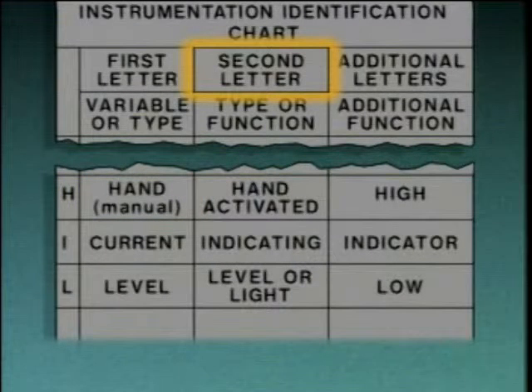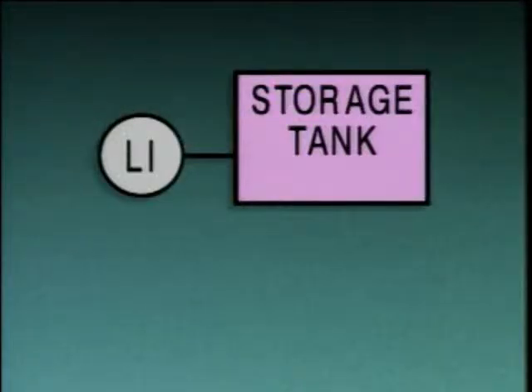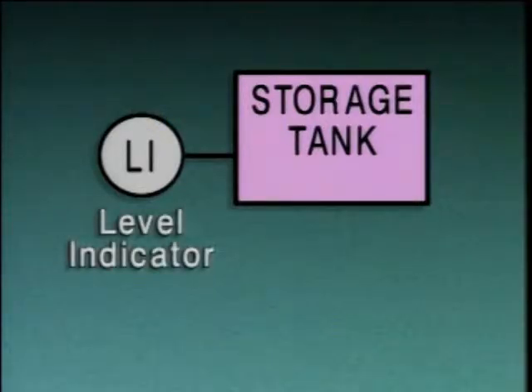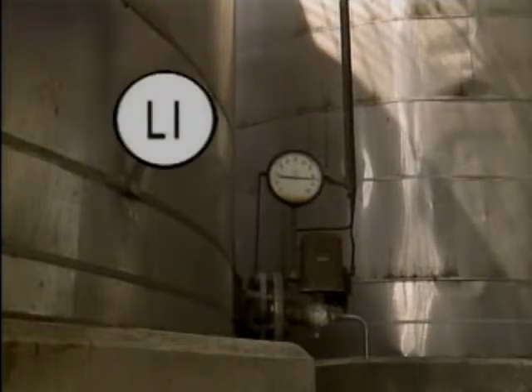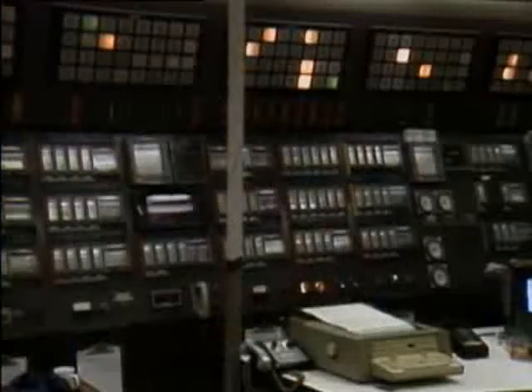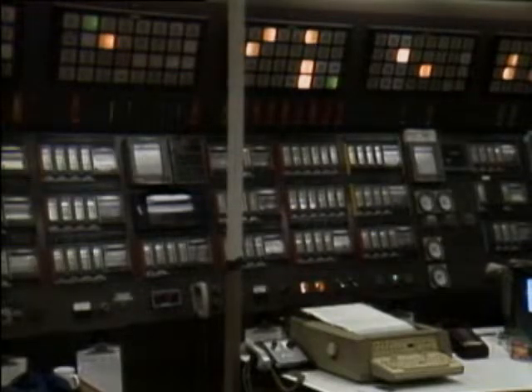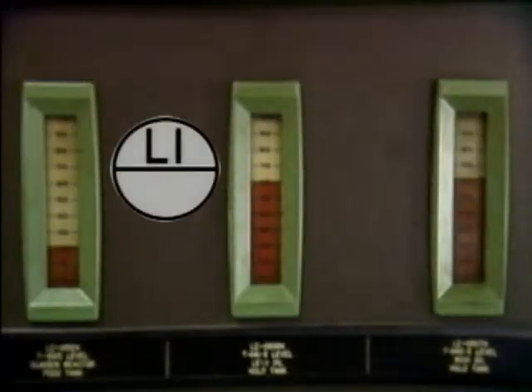The second letter in an instrument symbol usually indicates the type of instrument or its function. The second letter in this symbol is I. So this symbol represents a level indicator. Instruments that are located near a piece of equipment, like the level indicator for this tank, are referred to as local instruments. They're represented by a circle and letters. Remote instruments, which are typically mounted on a panel with other instruments in a control room, are typically identified by a line through the symbol, like the one here.